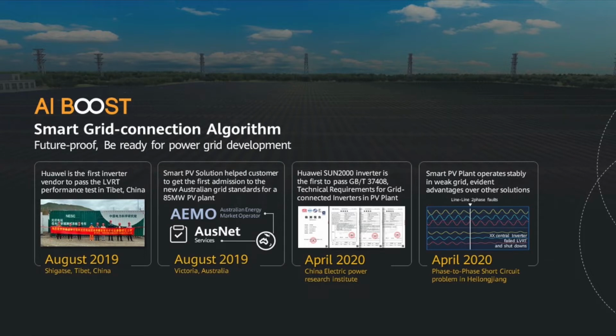And another real case occurred in northeastern China in April this year. A grid fault of phase-to-phase short circuit occurred and led to low voltage in this local grid. From the recording diagram, we can see that the central inverter in a 100 MW plant failed to ride through the low voltage and shut down for protection. At the same time, another 20 MW PV plant utilizing Huawei inverters accurately identified grid faults and ensured stable operation after successful low voltage ride-through. What's behind this case is that the SCR is getting lower after this 20 MW was grid connected.